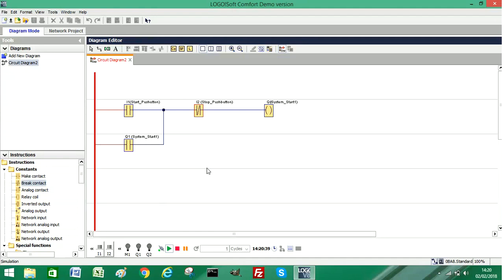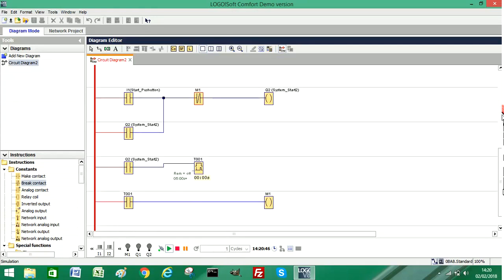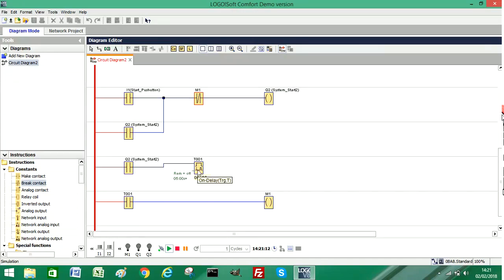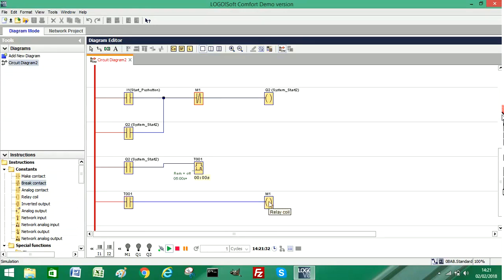The next step is how to create an automatic stop sequence. As you can see, we have a start push button, we have something that stops the system which is this M1 memory bit contact, and another start output Q2 that latches itself on. It also drives a timer. The timer will run for five seconds, and after five seconds, when the timer is true - because this is an on-delay timer - the timer output will become true and it will trigger our memory bit M1 which will stop the system automatically.